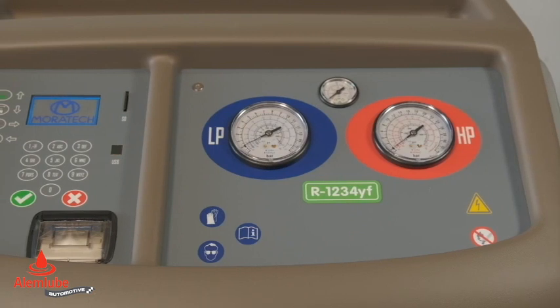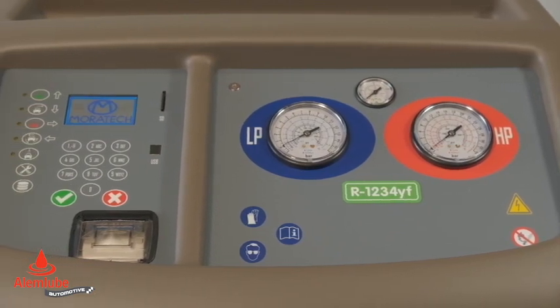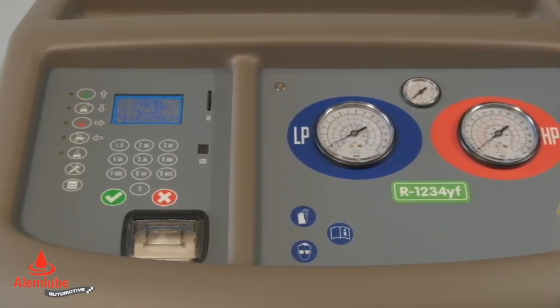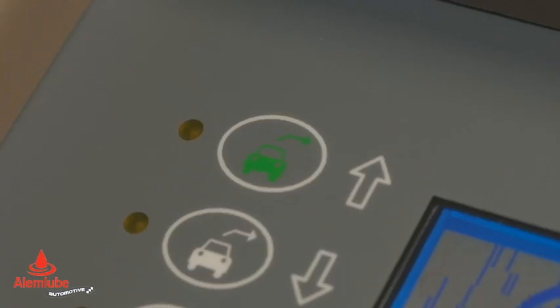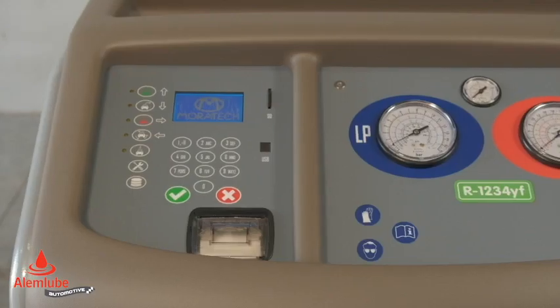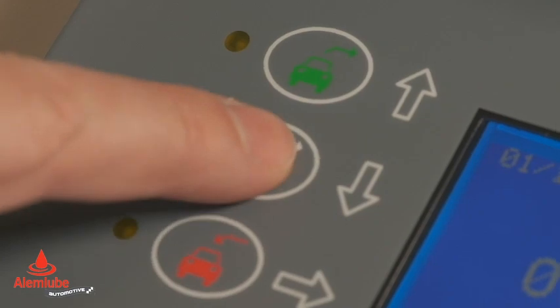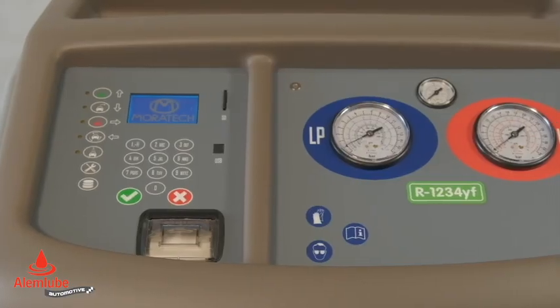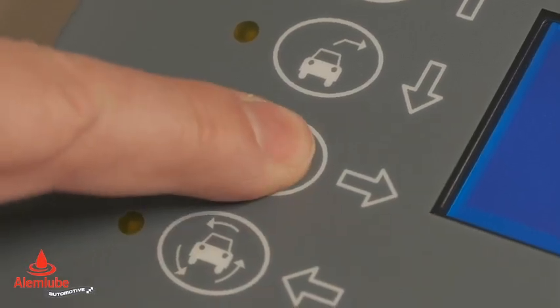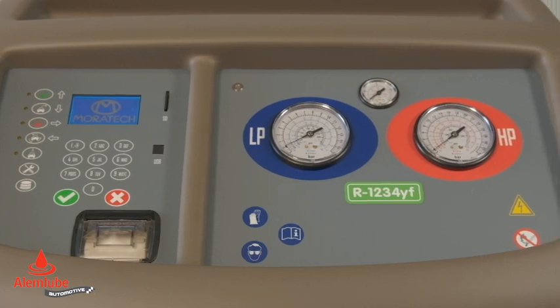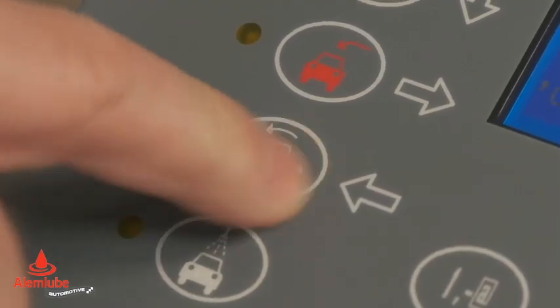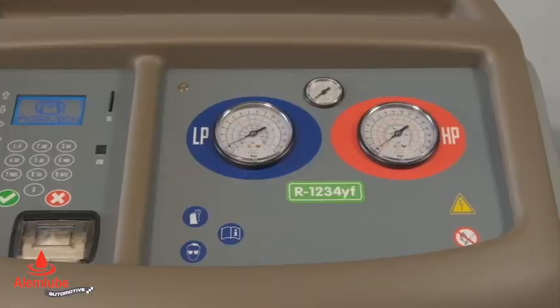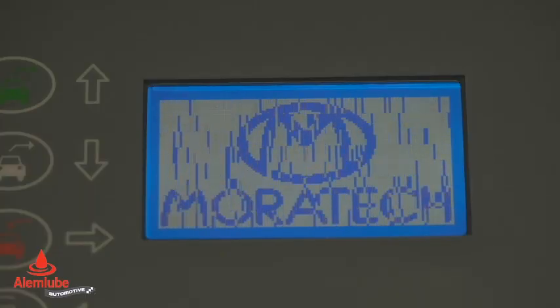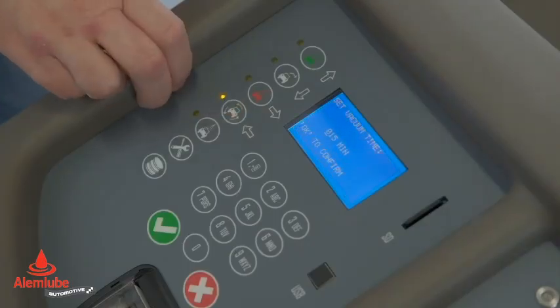It is possible to carry out maintenance on the air conditioning system using the single functions. Recovery, to extract the gas from the system. Vacuum, to remove moisture from the system. Prepare it for recharging. Charge, to recharge the system. Or in automatic mode, which automatically carries out the 3 phases in sequence. In this case we proceed using the automatic function.